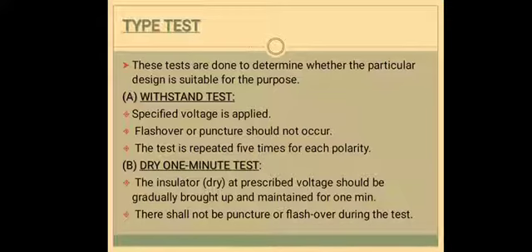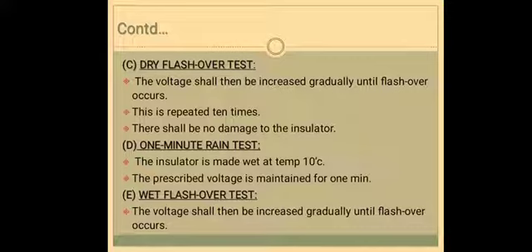Then next is the dry flashover test. In the dry flashover test, the voltage shall be increased gradually until flashover occurs. This is repeated 10 times and there should be no damage to the insulator when this testing occurs.